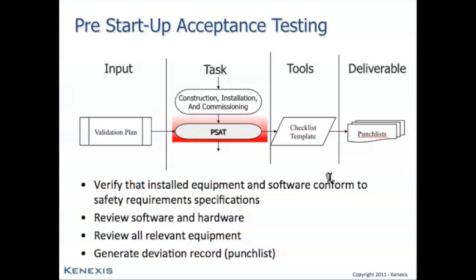All of the software and the hardware needs to be reviewed one more time to ensure that everything matches the safety requirement specification and is operational. And then all of the loops need to be tested. So the PSAT, or the validation, involves a full physical test from the field back to the control room and back out to the field for any safety critical actions that the FGS system will take. If any deviations from the FGS requirement specification are noted, they need to be documented in a deviation record, usually called a punch list, and then all of the items on the deviation record need to be satisfactorily resolved before the system can be put in operation in a safety critical application.